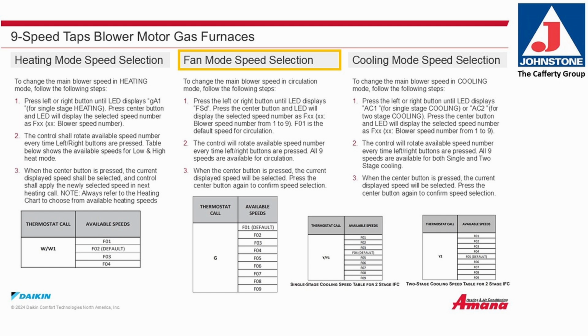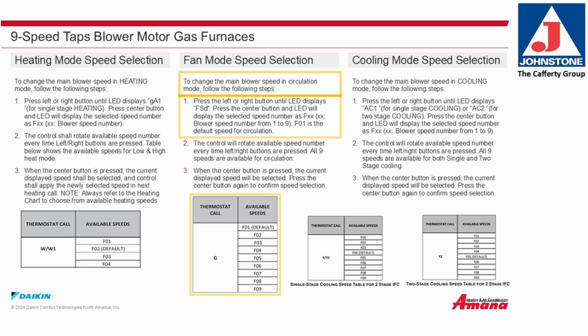Fan mode speed selection. To change the main blower speed in circulation mode, follow these steps. Press the left or right button until the LED displays FSD. Press the center button and the LED will display the selected speed number as F and 2 digits, 01 through 09.